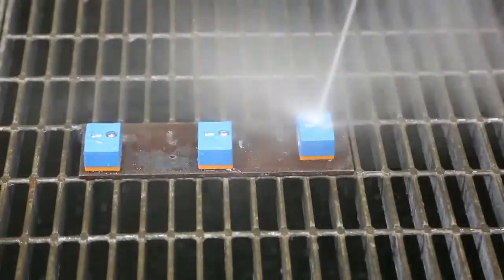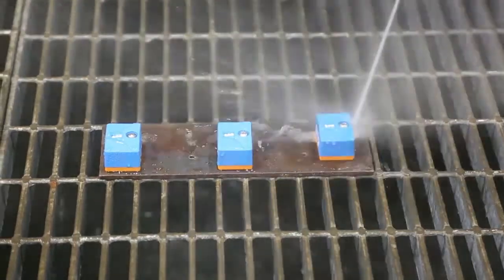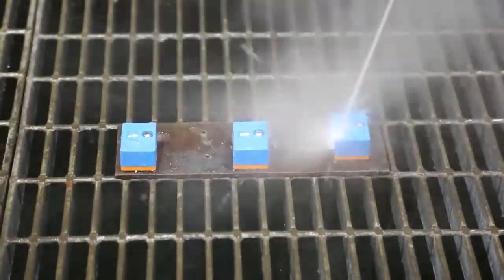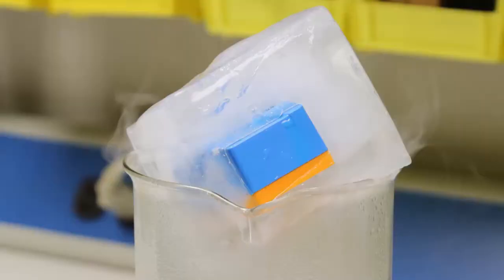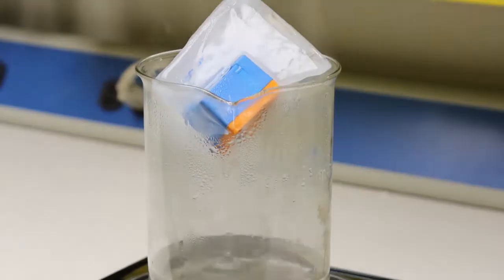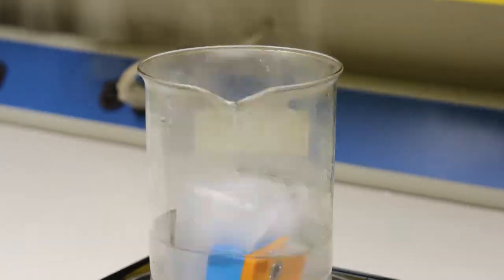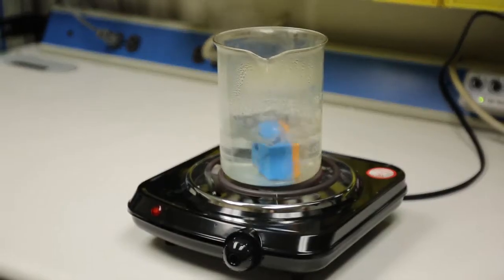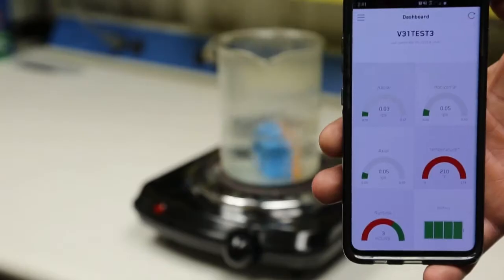It is unphased by high water pressure, but maybe changing the temperatures can make it sweat. What if we tried combining both pressure and temperature cycling by freezing the iAlert sensor in a block of ice? And then thawing it and heating it up to a rapid boil in a matter of minutes. Still works as expected.